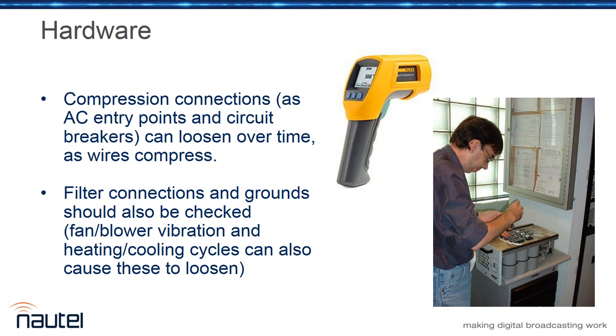This should be done ideally, it'll vary depending on your situation, but you want to do it at least every year or two, especially when you think about it, a transmitter's full of fans or has a big blower, it's sitting there vibrating and shaking hardware loose all the time. When we build it, we torque stuff down with specific torque settings for everything. I'm sure other manufacturers do too, but you want to check that stuff on a regular basis, especially in the power supply and high voltage circuits, because there's nothing better than a high voltage or high current power supply with a loose connection in it. Nothing better for the light show and entertainment value, and our parts department will love you.